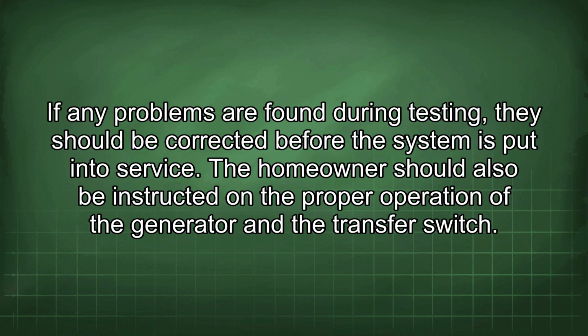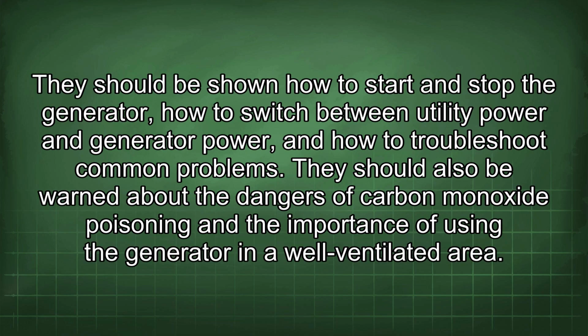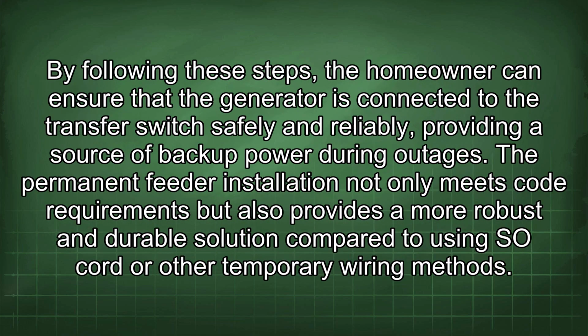The homeowner should also be instructed on the proper operation of the generator and the transfer switch. They should be shown how to start and stop the generator, how to switch between utility power and generator power, and how to troubleshoot common problems. They should also be warned about the dangers of carbon monoxide poisoning and the importance of using the generator in a well-ventilated area. By following these steps, the homeowner can ensure that the generator is connected to the transfer switch safely and reliably, providing a source of backup power during outages.